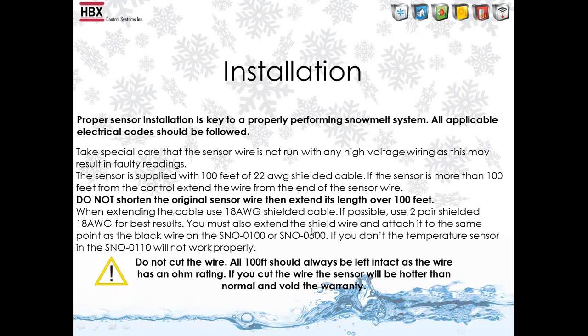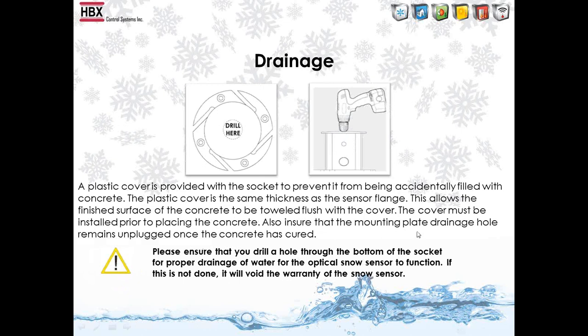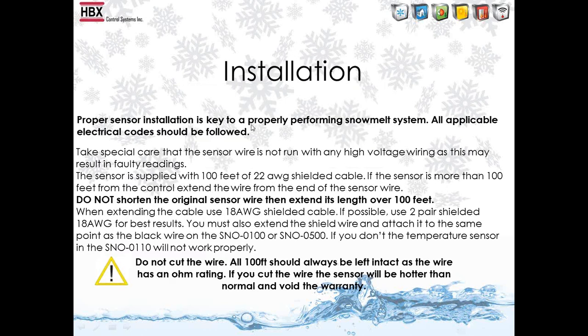If we get a snow melt sensor back to us that has been shortened, the warranty is instantly voided. So keep that in mind. One of the other problems we found was that people weren't doing proper drainage on the control. Let me go back to the shortening of the wire. We do put a sticker right on the face of the snow melt sensor now that says "Do not cut the wire." We've gone to great lengths to make sure that people don't shorten the wire, because, like I said, it can wreck the control.